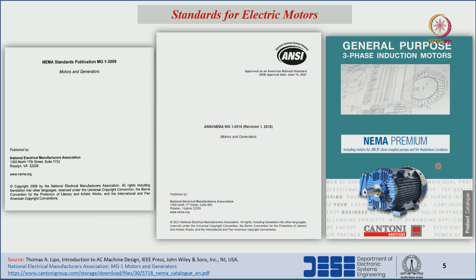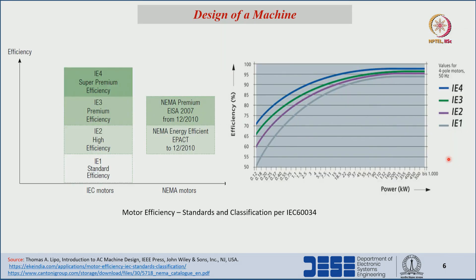The NEMA standards MG1 2009 and the revised 2018 version with approval date June 15, 2021 are available. With respect to efficiency classes, the IE4 standard represents very high efficiency; IE3 represents premium efficiency, slightly less than IE4; IE2 represents higher efficiency but less than IE4 and IE3; and IE1 represents standard efficiency — the lowest of the four classes according to IEC standards.